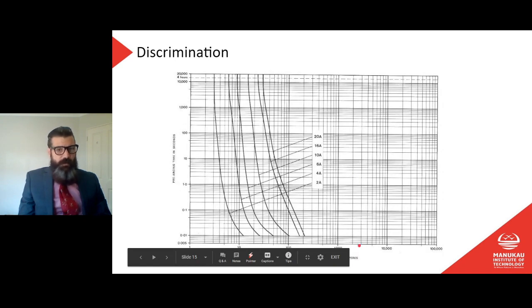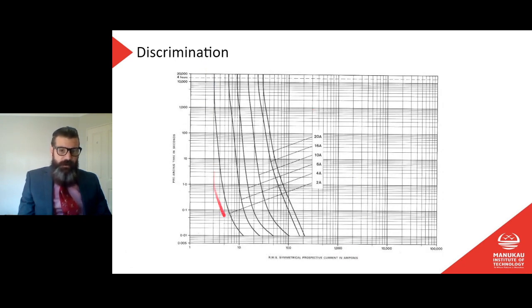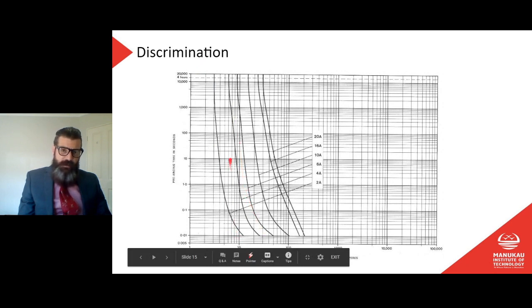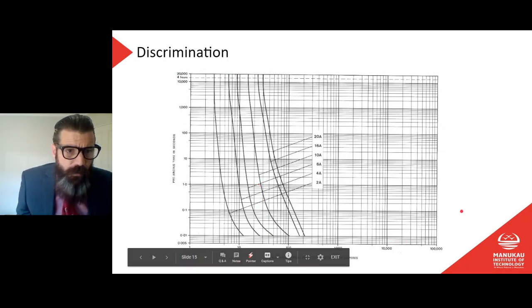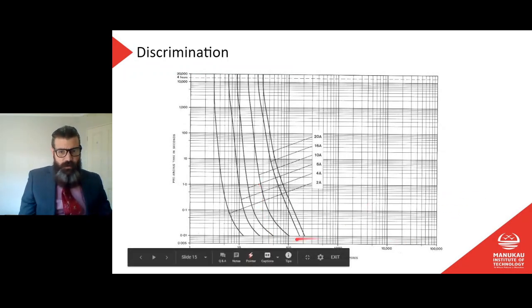So let's have a look at the graph. What does that mean? So here's our time current characteristic for various different devices. Each one of these lines here represents, is it a circuit breaker or a fuse? I'm not sure. It doesn't matter. Let's say a circuit breaker. So this line here is a 2 amp circuit breaker. This line here is a 4 amp, 6 amps, 10 amps, 16 amps, 20 amps.